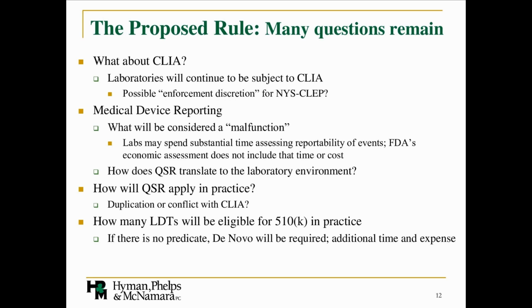And then going back to GMP or the quality system, how will this translate? Because even FDA acknowledges that there are differences between laboratories and traditional device manufacturers, and the QSR is tailored to traditional device manufacturing in terms of qualification of suppliers, design history files. There's no guidance in the proposed rule about how in practice a laboratory would comply with Part 820, which is where the QSR regulations are codified.